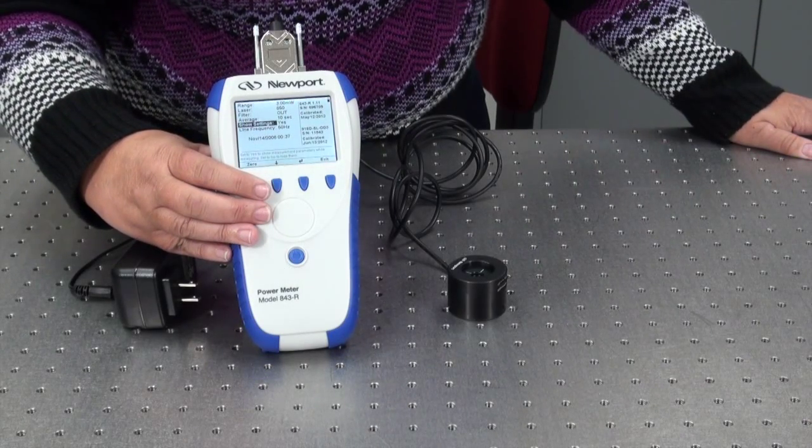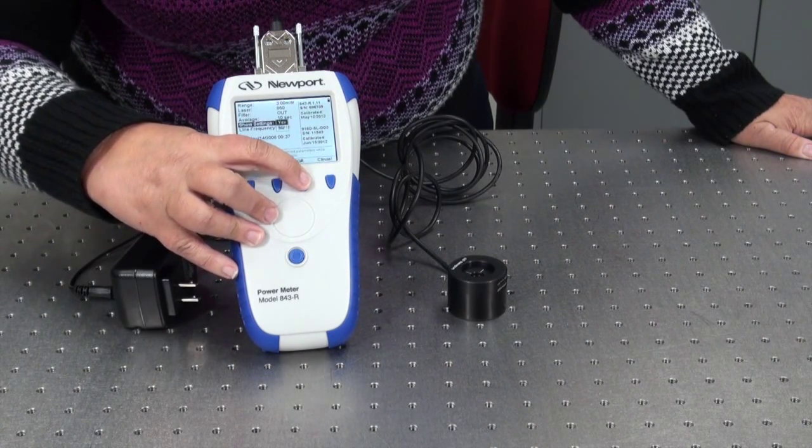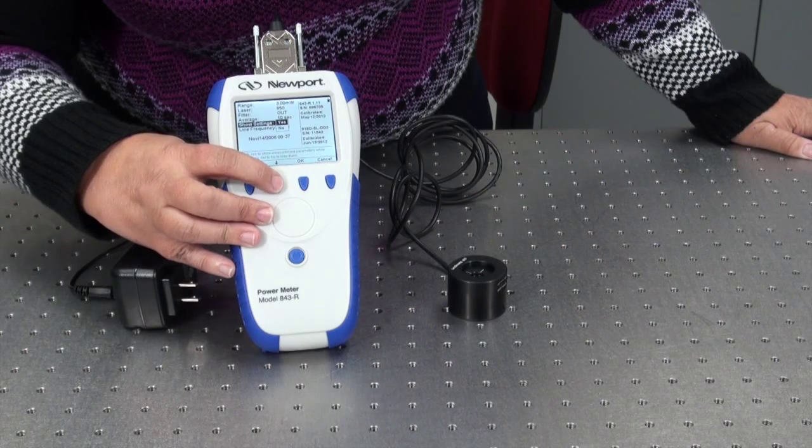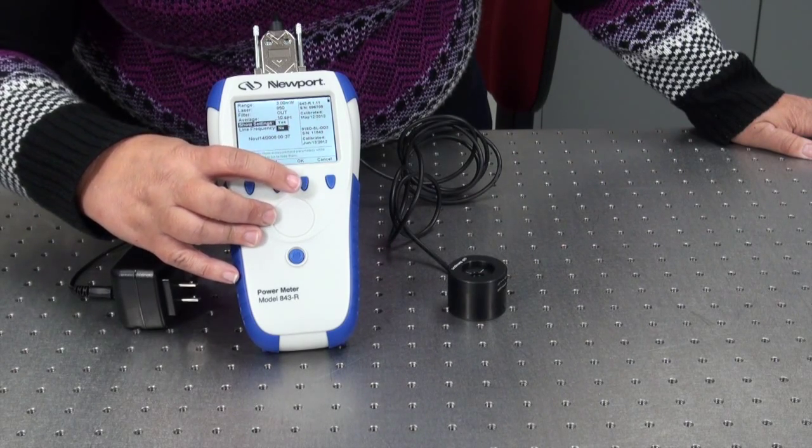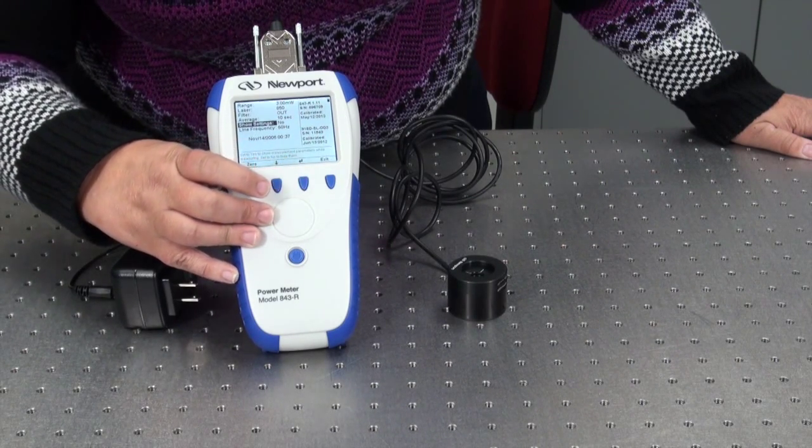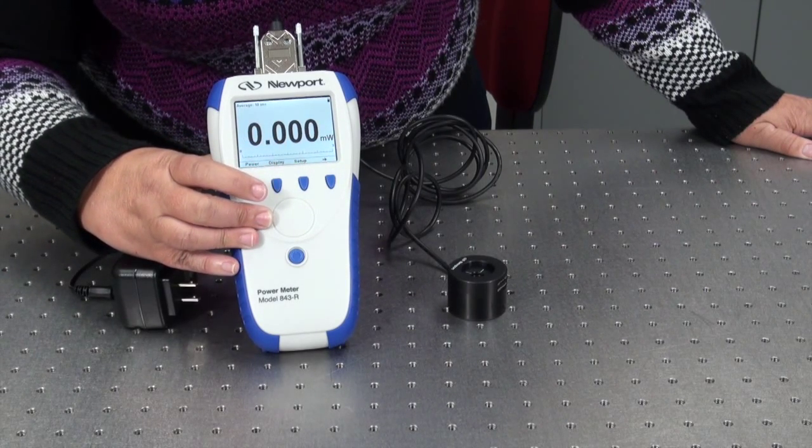The show settings menu is used to display or not display the settings for the laser wavelength, power range and detector model and serial numbers on the power measurement screen. Choosing a setting of yes will display these settings. Choosing a setting of no will not display these settings and will show a larger graph.